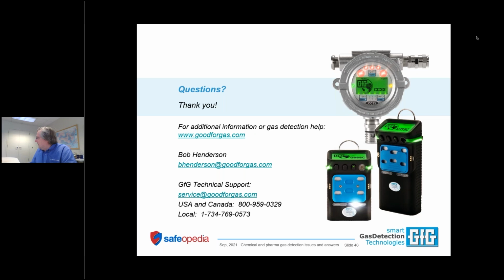Well, if you're using a docking station, typically we are putting the instrument into the docking station, and the docking station does its thing. And its thing can be to perform a daily test, or if it's now time for a full calibration, it can automatically do the full calibration. But if you pick the daily test, technically what the docking station is doing is going a little bit beyond a bump test. A bump test, according to OSHA and the ISEA, the International Safety Equipment Association, is purely qualitative. All you're doing is exposing the sensors to gas in a concentration of gas that is high enough to cause the activation of the alarms.